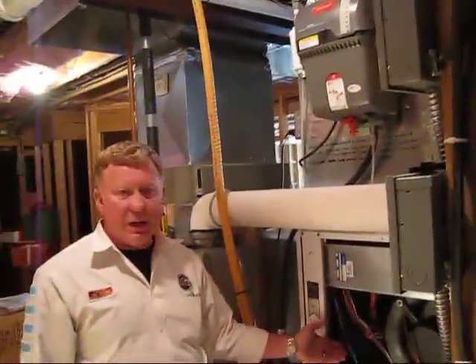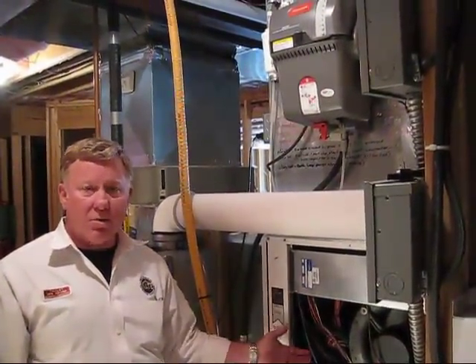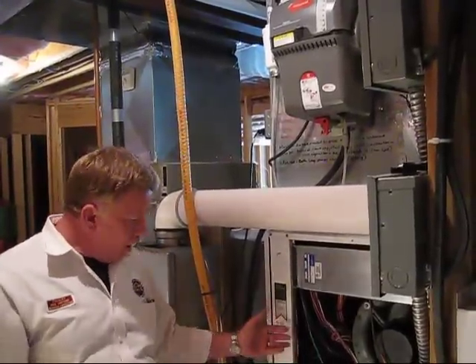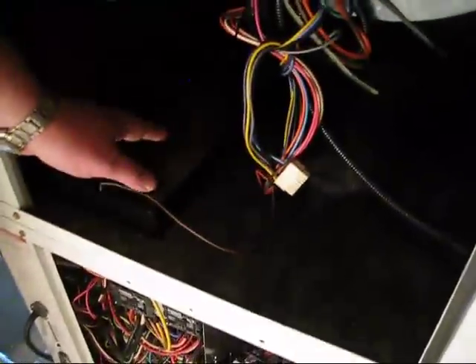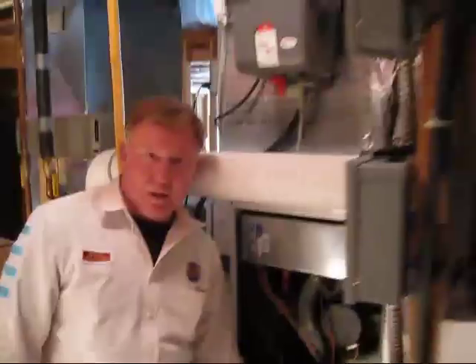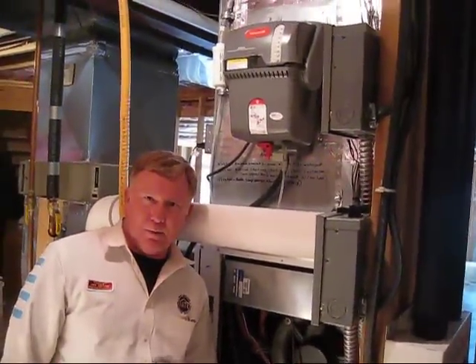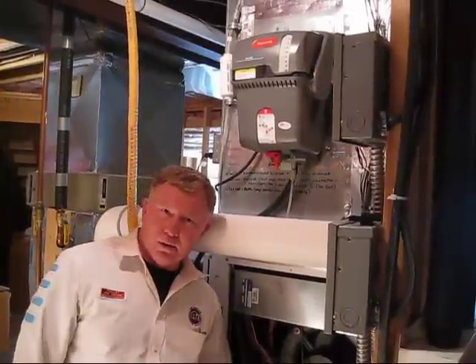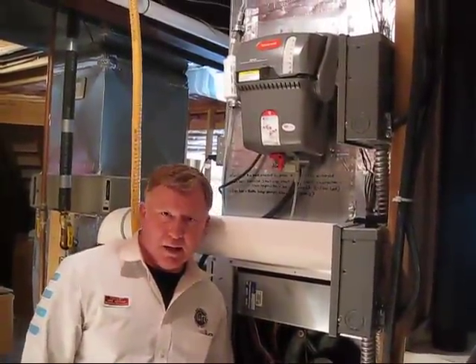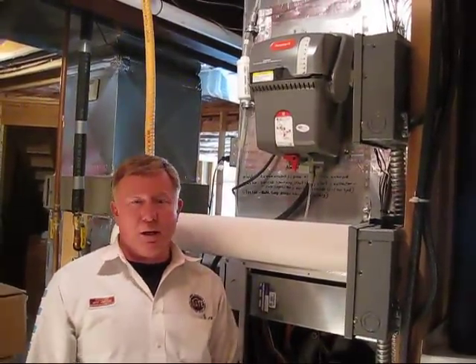But a piece of equipment like this one, which is a geothermal, ultra-high efficient piece of equipment, also has a condensate pan within the unit that you cannot just simply wash out or rinse out. It has a special sensor in it that, if it's not properly cleaned, something as simple as a spider web can cause this equipment to fail and not operate until someone comes out and checks that. It will think it's full of water when it is not. It's a very simple thing, easily missed.